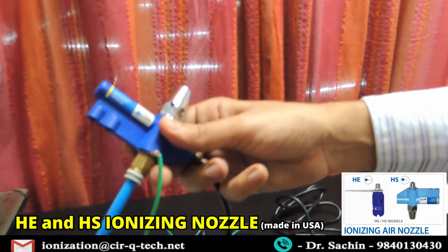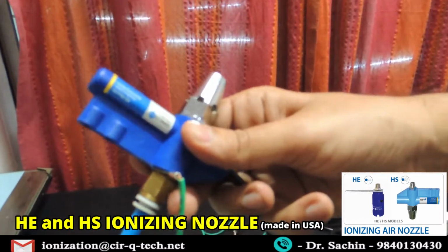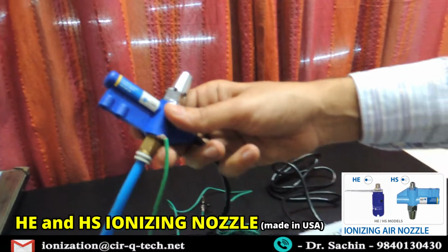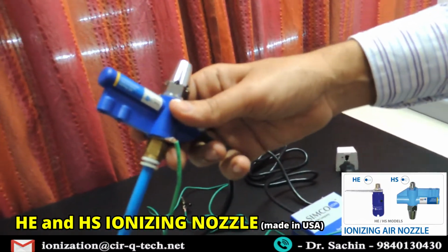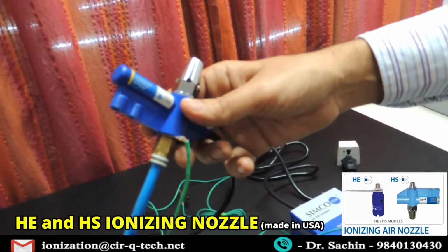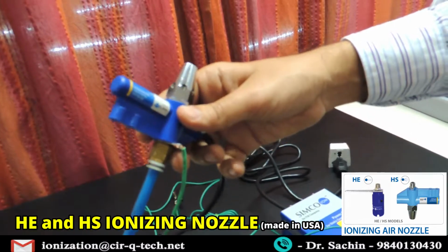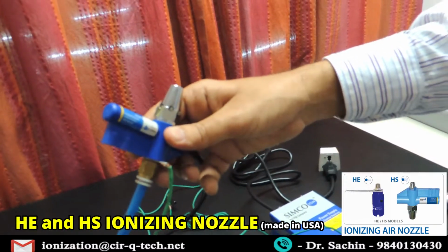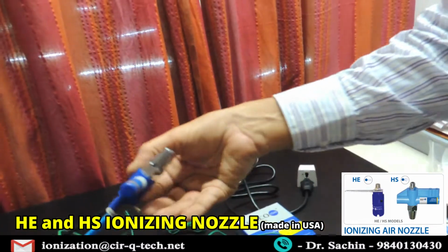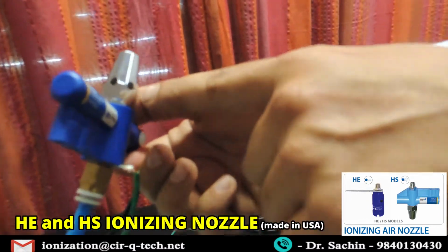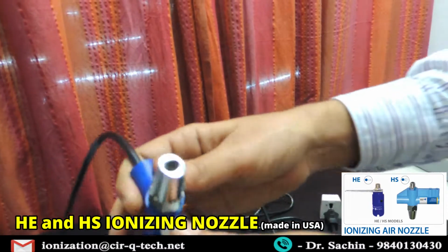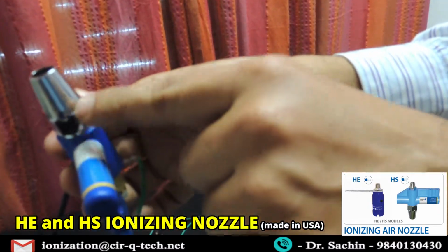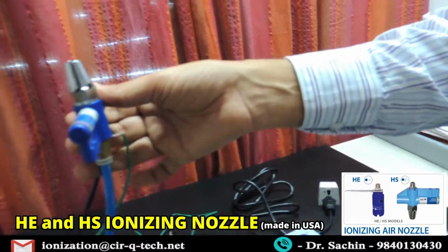End nozzle. This is the Simco Ion US make, and this is typically an end nozzle. The end nozzle is one which is put at the last. For example, if you have a daisy chain, you will have multiple through nozzles, and at the last you will have this end nozzle. Typically you can also see you will have these flare nuts, so they will have certain openings for the emitter pin to be available for cleaning purposes and so on.